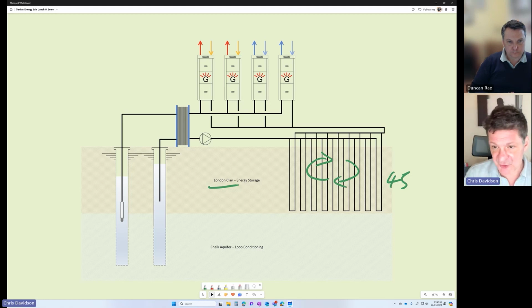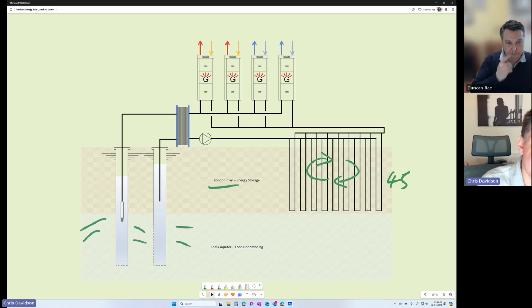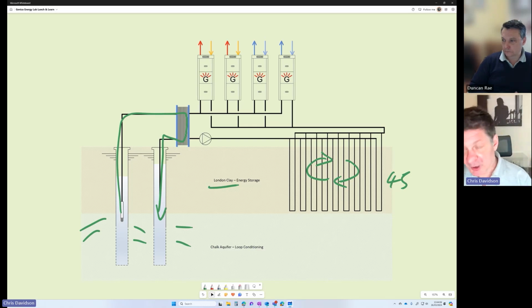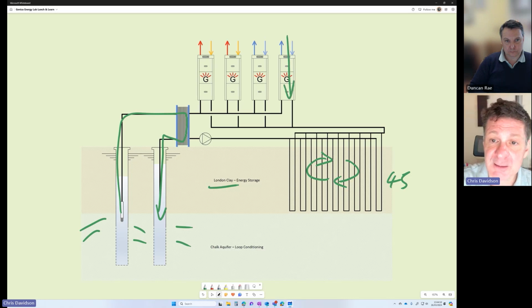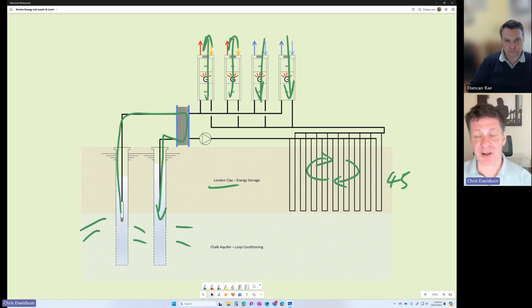We've got other things we can do with that ground loop as well. We can use water wells, which are using the water in the chalk here, and we can temper that ground loop using that water in the chalk. It's a bivalent system, so we can schedule loads on and off as well. So we can take cooling and put heat into that loop. We can use it for heating to take heat back out of that ground loop.